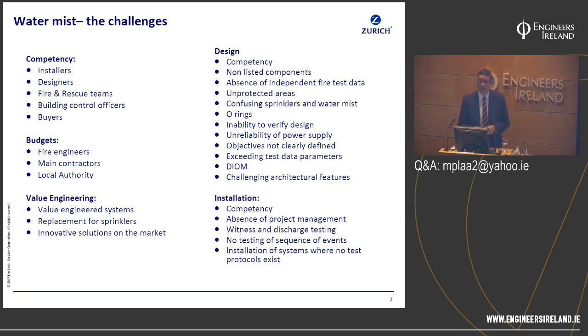Often the suppliers of these systems cannot verify that the water mist system is fit for purpose. It should be backed up by independent fire test data for each and every application in a building. And often that lack of independent fire test data is conveniently forgotten or not demonstrated by the installer. And there can often be many, many unprotected areas. I come across buildings such as schools where we've got water mist, but there's lots of unprotected areas. So it's sold as a property protection system, but in fact, all it really is, is a life safety system.